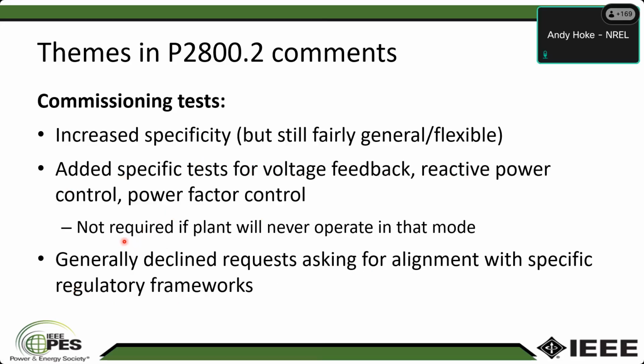Those, I guess we should point out, are only required, or, the best way to say it is probably, they're not required if the plant will never operate in the particular mode that would be tested. You only run the test for the modes that the plant would operate in. That, again, is something we could debate. There are some people who would say, no, we should run all the tests. We want every plant to be capable in case we need it in the future, but that's not the way the standard is going. There were also some requests to align the standard with specific regulatory frameworks. We in general decline those requests and try to just keep it general.